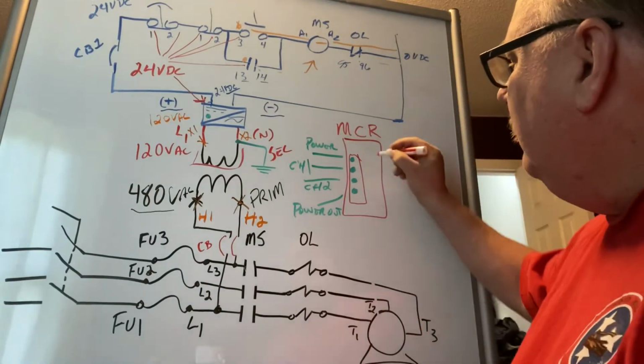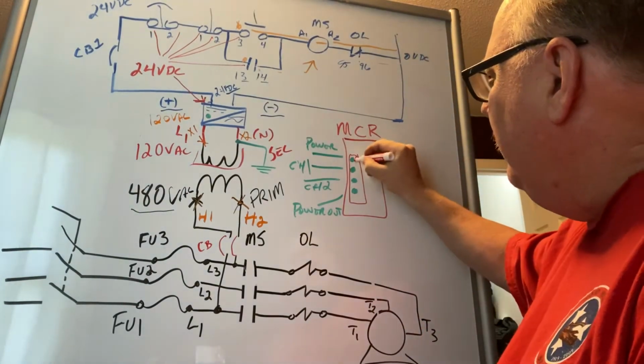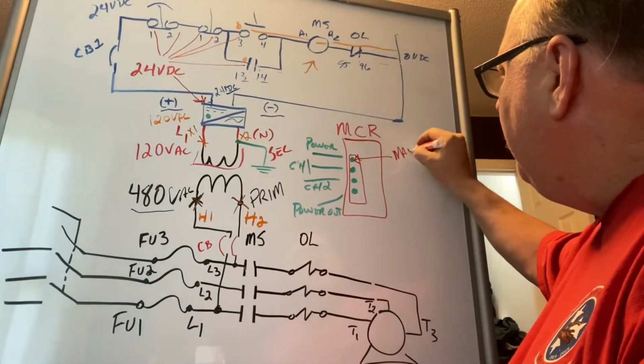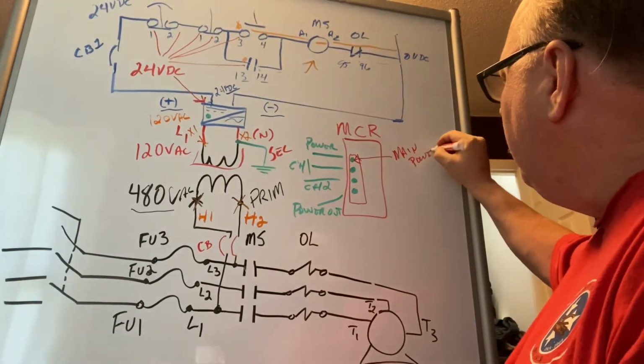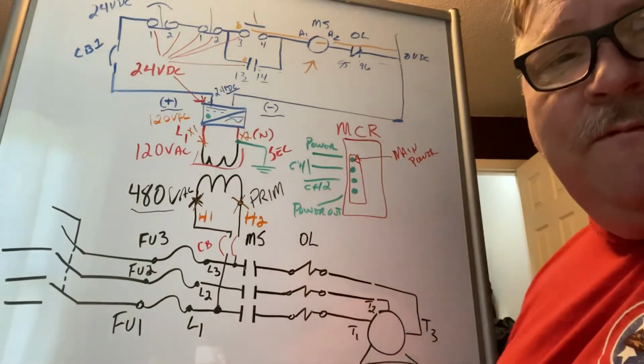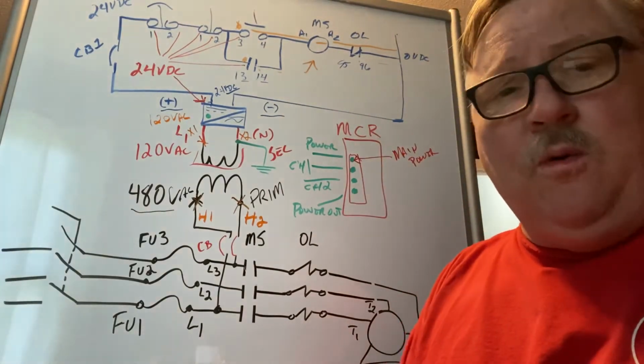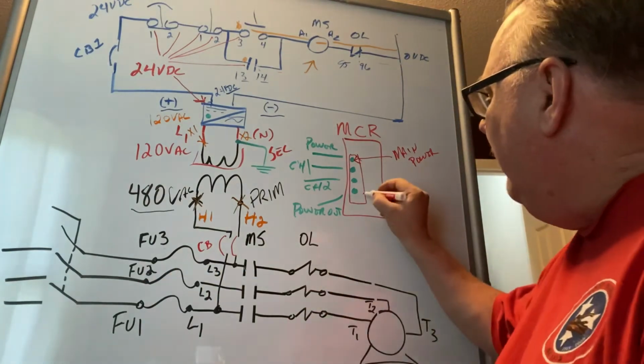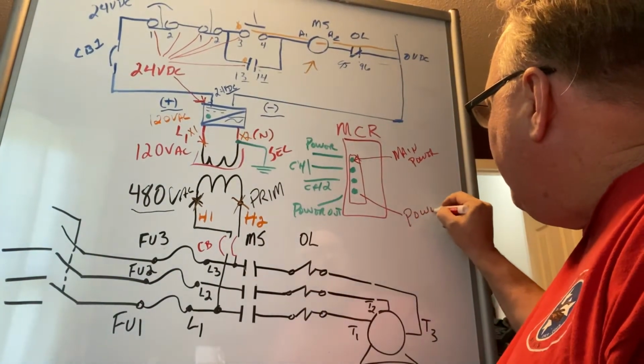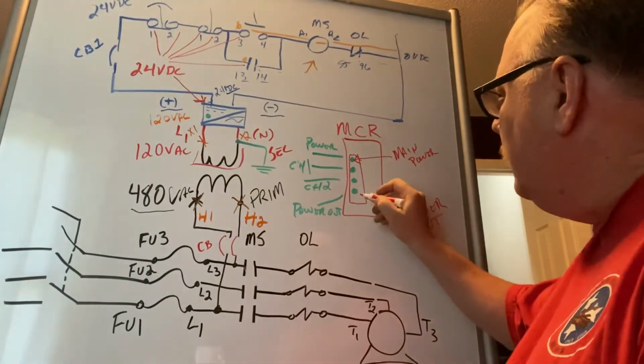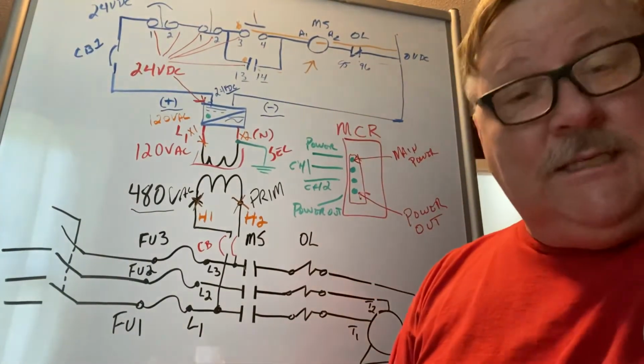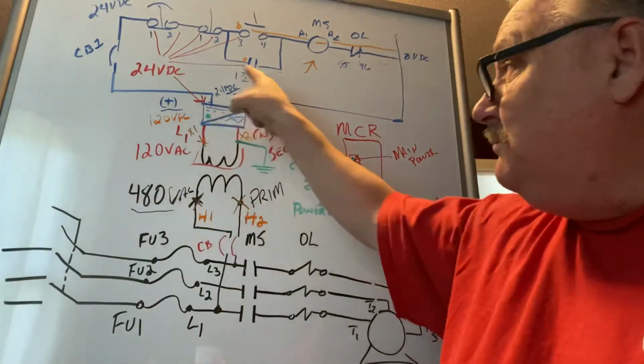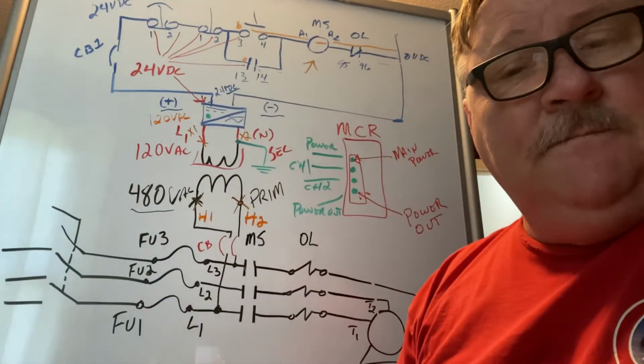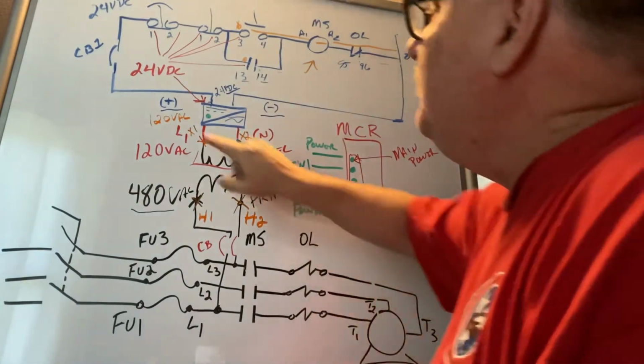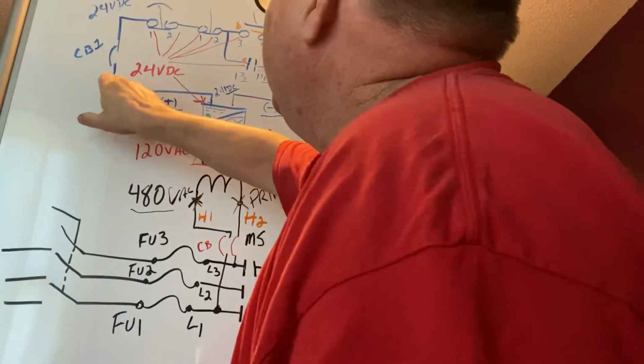And remember, the key ones is if you don't have this one here, which is your main power, that's telling you that that safety device is getting the 24 volts it's supposed to get, or the 120, if it was a 120 volt circuit. And then this one down here is the power out. If that bottom green light is not on, you're not going to have any power that's up here.